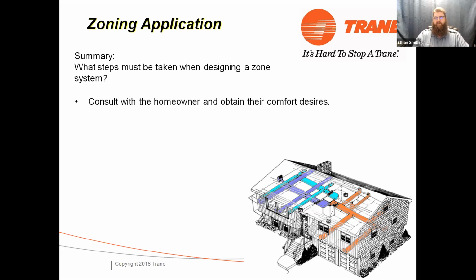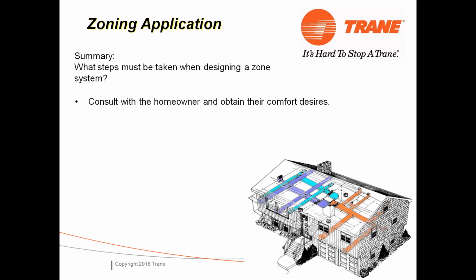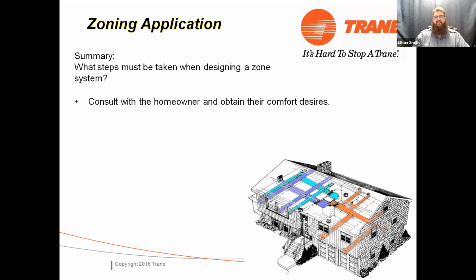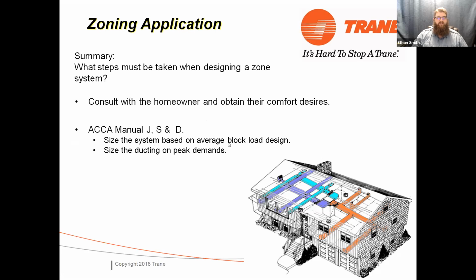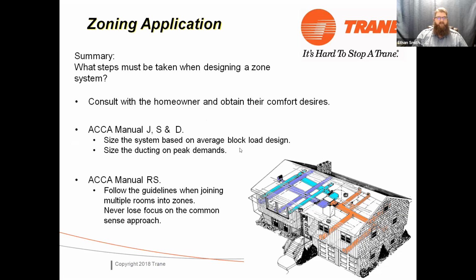Once you know your load and your airflow capacities, what can you then decide? How big of a unit you need. Yeah, you start getting into equipment selection. How big? How many stages? Yeah, stuff like that. Okay. The point is, guys, start with the homeowner. Make sure they understand what's possible, what's not possible, and then do the work. You got to do the work. The guys I talk to on a regular basis that have problems with the zoning systems don't do the work. They just try and wing it. You got to go through, make sure your stuff conforms. Do that load, do that duct. Okay. And then select your equipment.